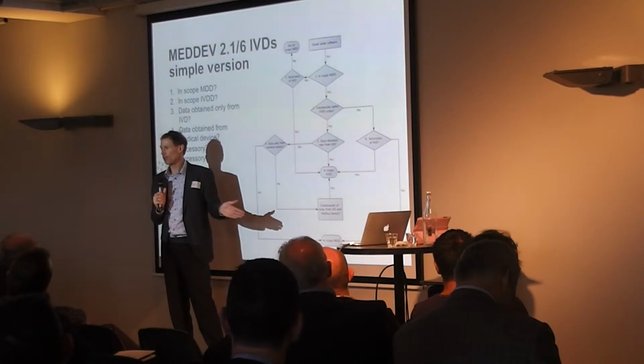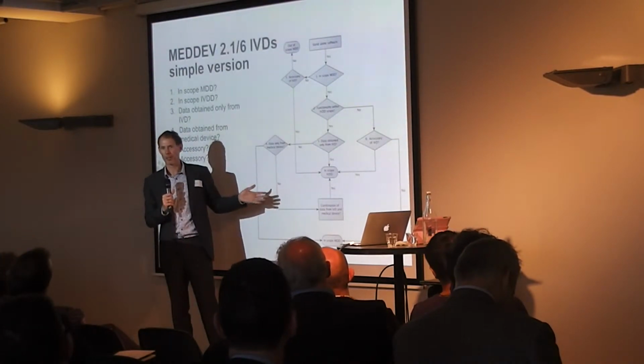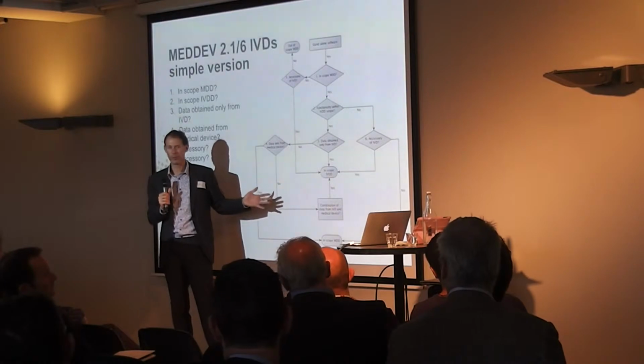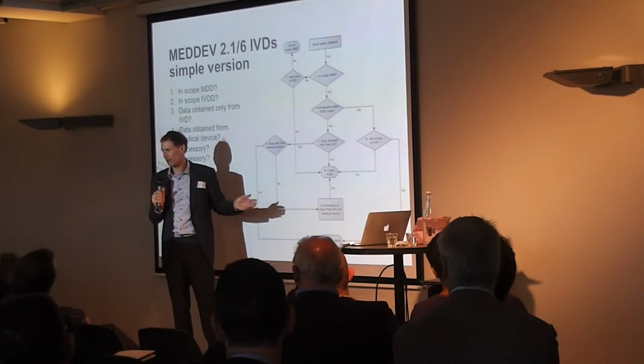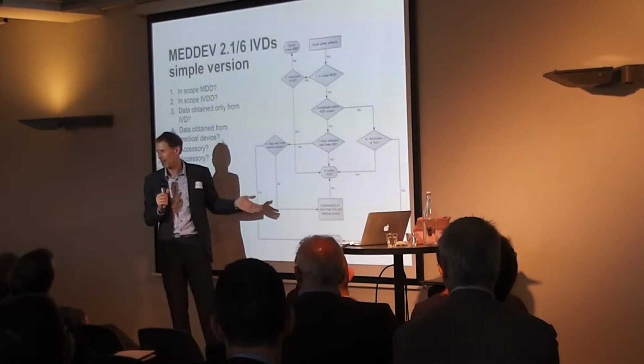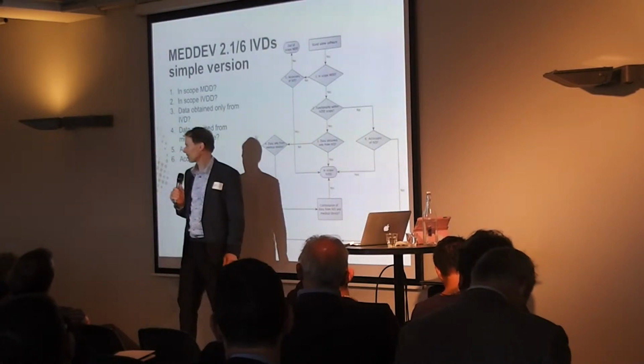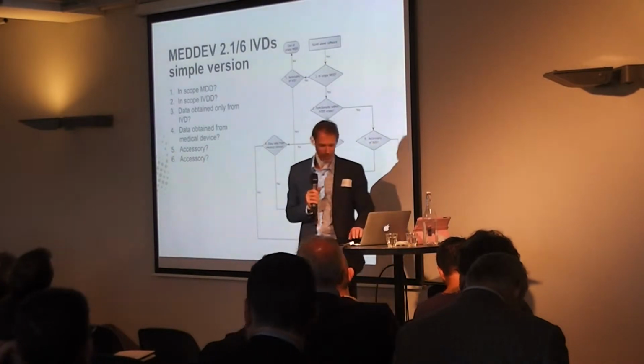In that case you have to seriously consider that your software can be an in vitro diagnostic device and needs to be CE marked under another directive than the Medical Devices Directive. It's a directive that looks a lot like it, but still has different criteria. So be careful of that.